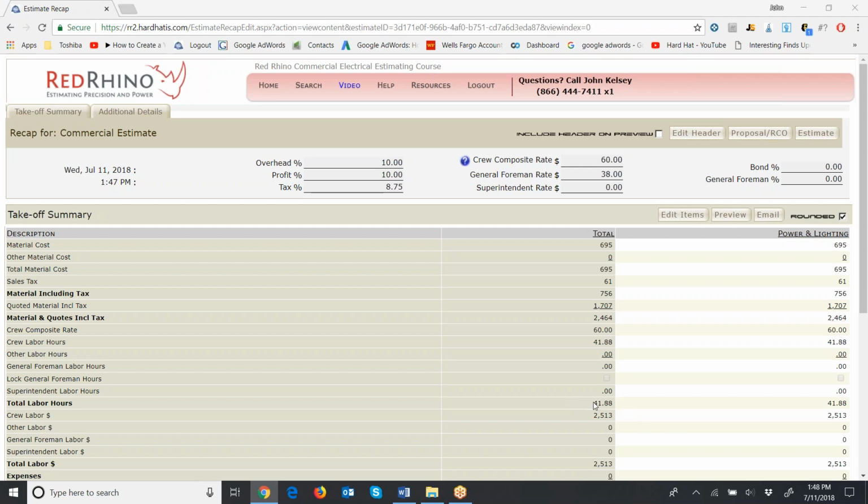Well, I have 41 hours in this job. I don't know if that's enough. Let's say I think it should be 2 guys, 3 days. If it was 2 guys, 3 days, I need 48 hours in this estimate, but I only have 41.88. Again, 16 hours times 3 is 48 hours. Now I'm going to add labor because I think it should be more time. Again, you get my drift. You do the estimate, then you evaluate it, then you tweak it, okay?